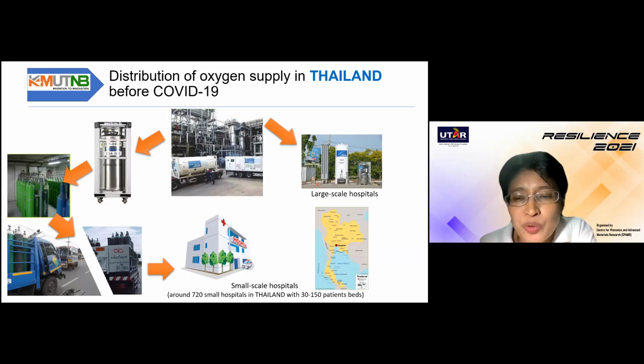Before the pandemic, large-scale hospitals needed bulk supplies of liquid oxygen because bulk liquid is cost-effective. Liquid oxygen is delivered to fill the oxygen tank located outside the hospital buildings. Oxygen is drawn off as needed and passed through a pipeline to a vaporizer first, where it is turned into gas before it is piped to individual wards of the hospital.